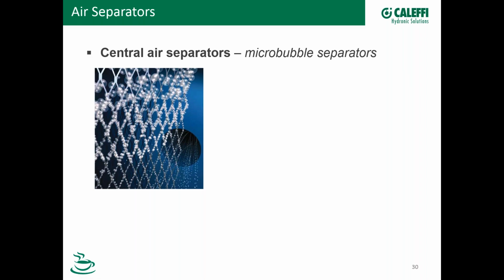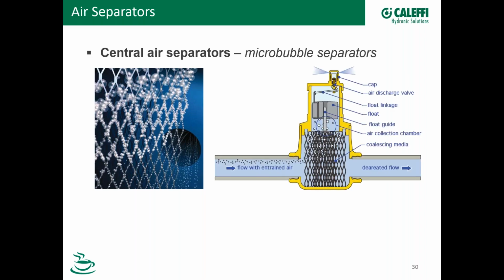Now, what helps this whole process is that when you come into an air separator, you have basically a large barrel. It creates a low pressure, low velocity zone, and that zone where the water slows down promotes the coalescing of the bubbles on the element and the buoyancy. So again, an air separator is not a filter, so they don't have much of a pressure drop. I'm going to talk about that in a minute. And so they don't typically require service. They just do their job.